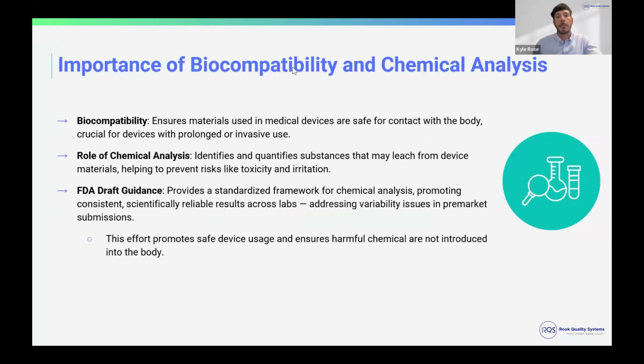On the importance of biocompatibility and chemical analysis: biocompatibility, like I said, ensures materials used in medical devices are safe for contact with the body. This is really critical for devices with prolonged contact or implant or invasive use devices. The role of chemical analysis identifies and quantifies the substances that may leach or extract from the materials, helping to prevent risks like toxicity and irritation, allergic reaction, sensitivity, all of these things that are within the scope of biocompatibility as well.